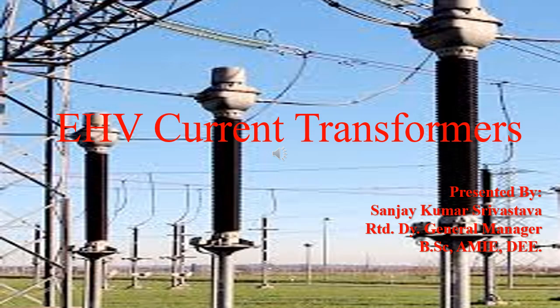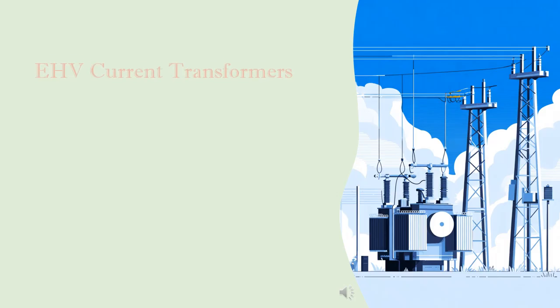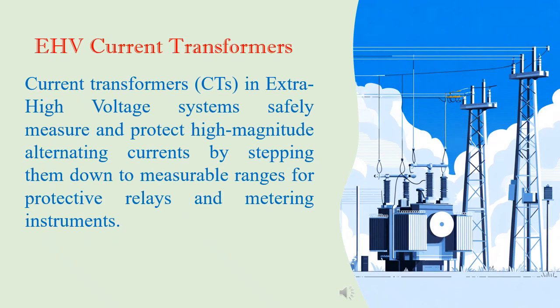EHV Current Transformers, presented by Sanjay Kumar Srivastav, retired DGM. Current transformers in extra high voltage system safely measure and protect high magnitude alternating current by stepping them down to a measurable range for protective relays and metering instruments.